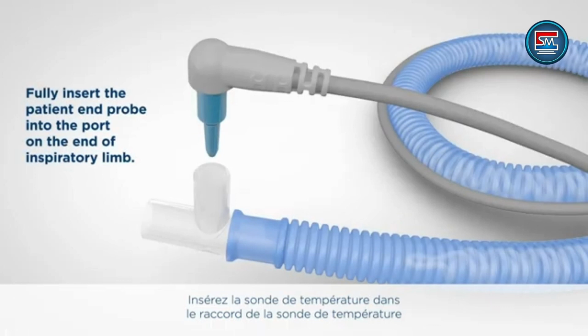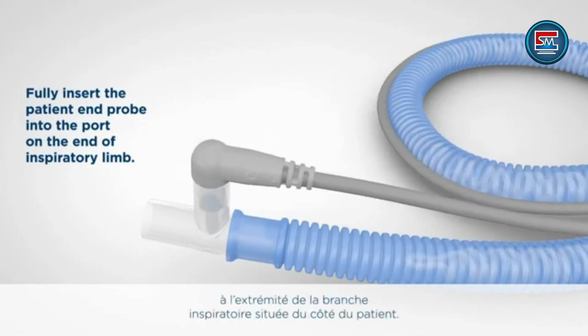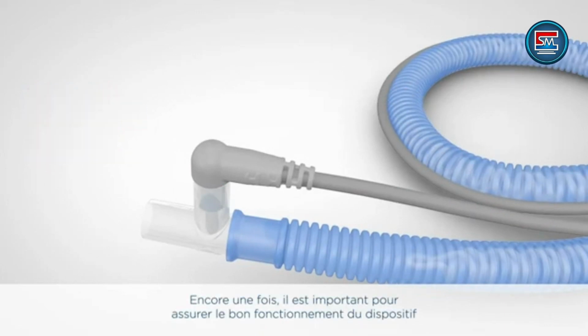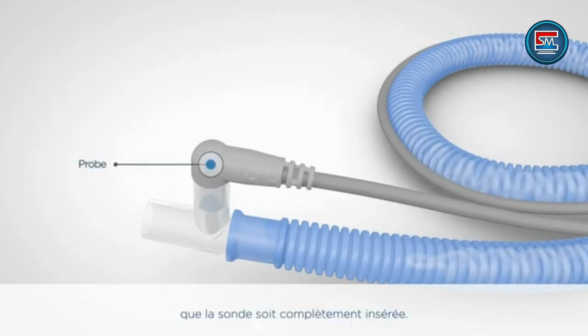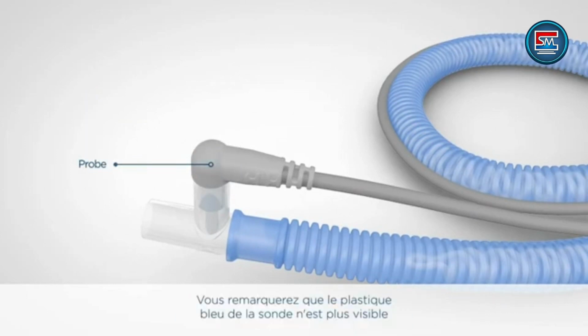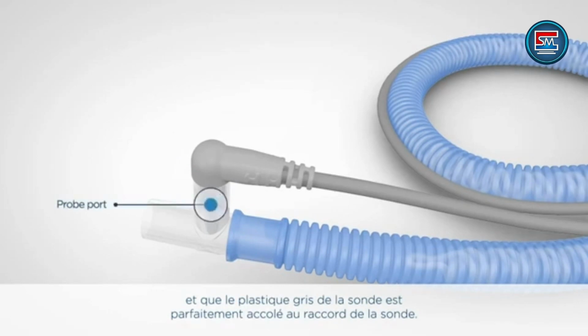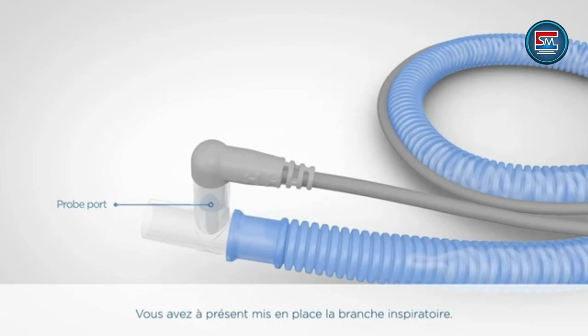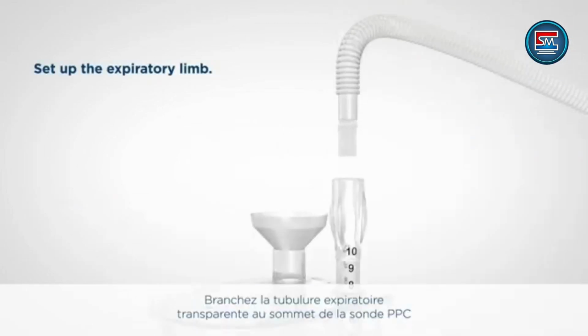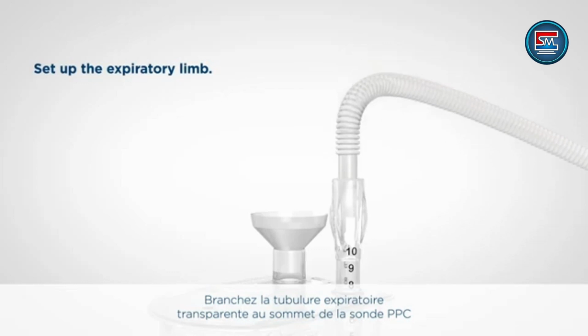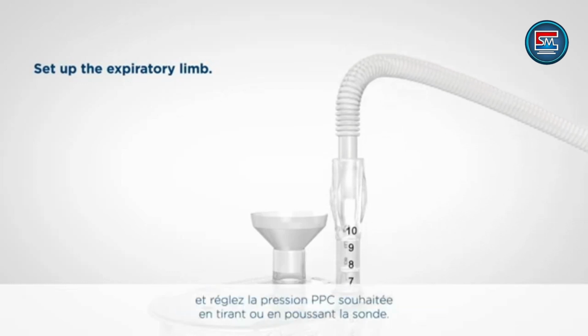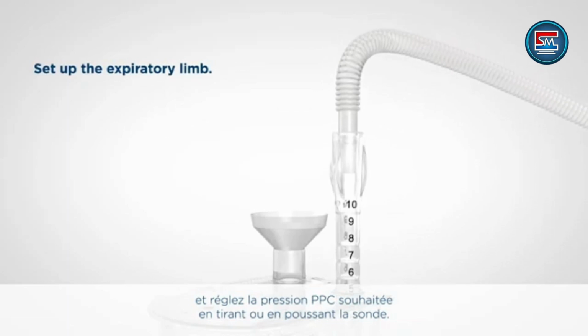Insert the temperature probe into the temperature probe port at the patient end of the inspiratory limb. Again, it is important for correct function of the system that the probe is inserted fully. You will notice that there is no blue probe plastic showing outside the circuit and the grey plastic is seated against the probe port. We have now set up the inspiratory limb. Connect the clear expiratory tubing to the top of the CPAP probe and set the desired CPAP pressure by pulling out or pushing in the probe.